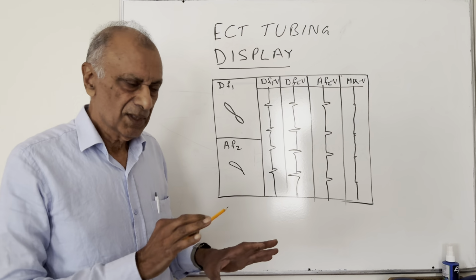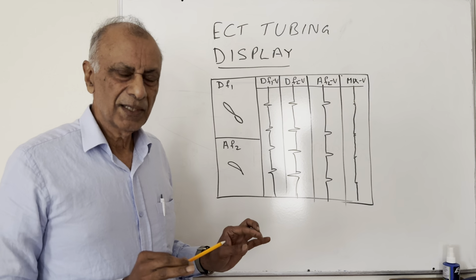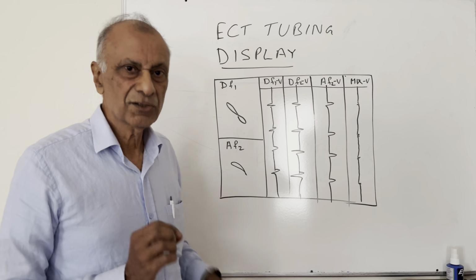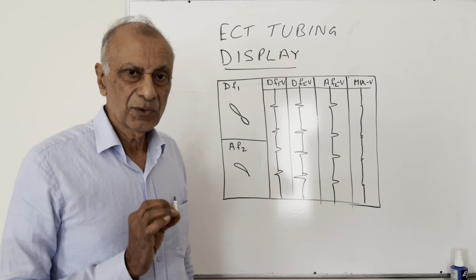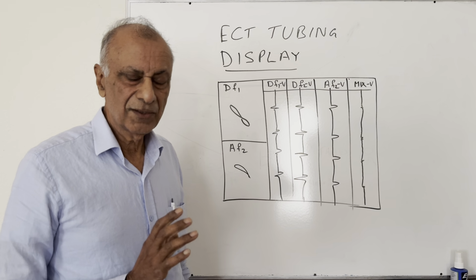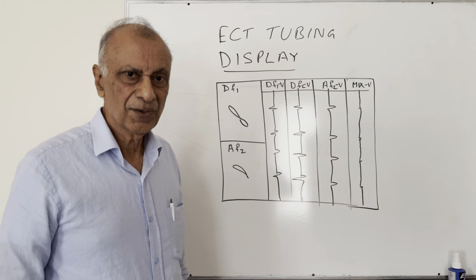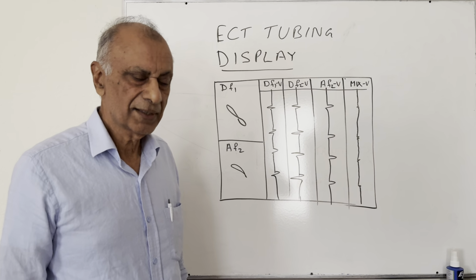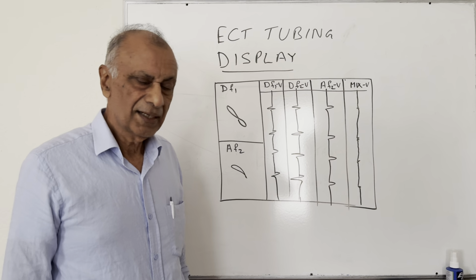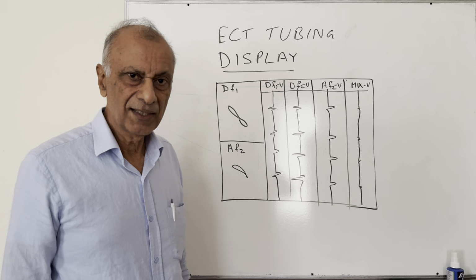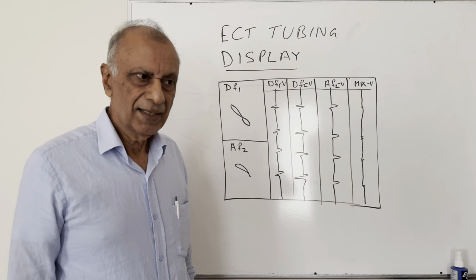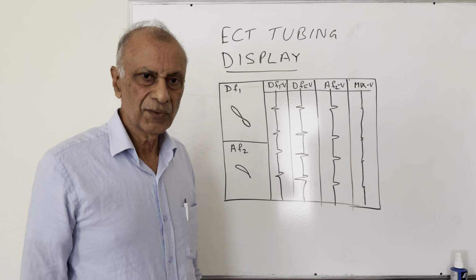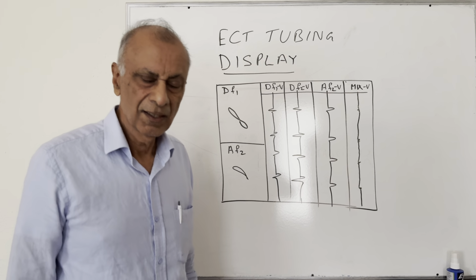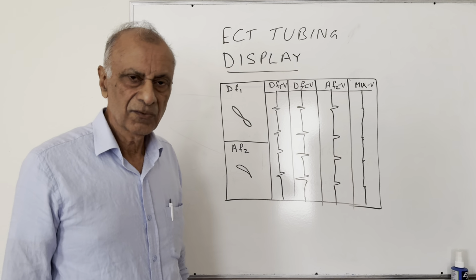So it's a process. This tubing inspection is a process, and it has to be done the right way to do a good inspection, whether you're doing stainless steel or brass or Inconel tubings or titanium in the condenser tubes. So it's a wide range of applications, and if you do it right, you will actually get very good inspection of the heat exchanger tubes, 100% length.